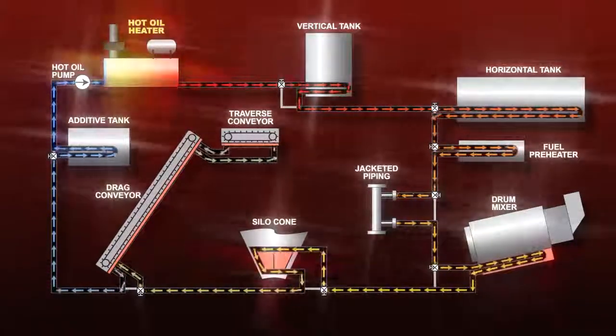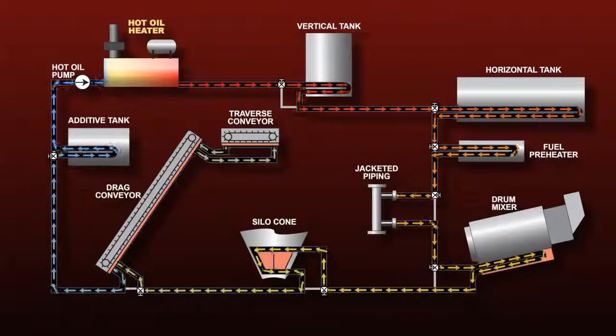Moreover, the heater will shut down if oil flowing through its coils is too slow to convey the amount of heat being generated.